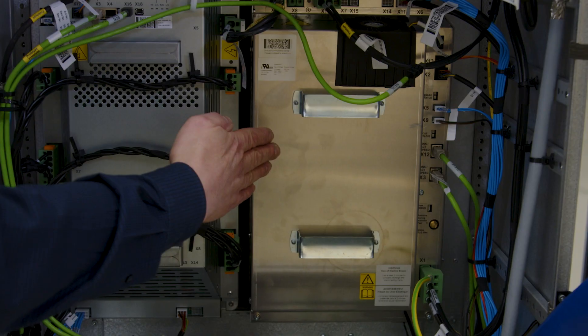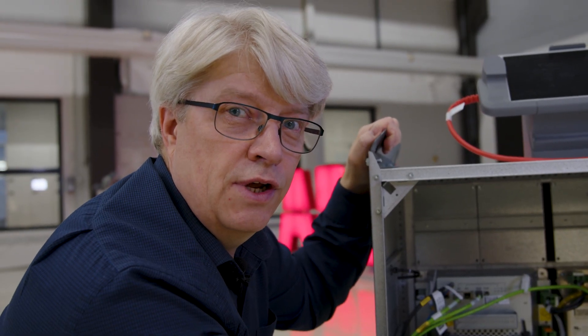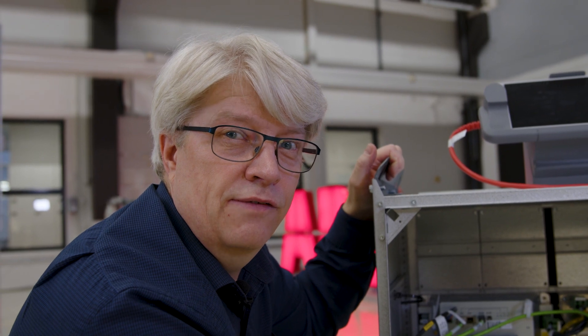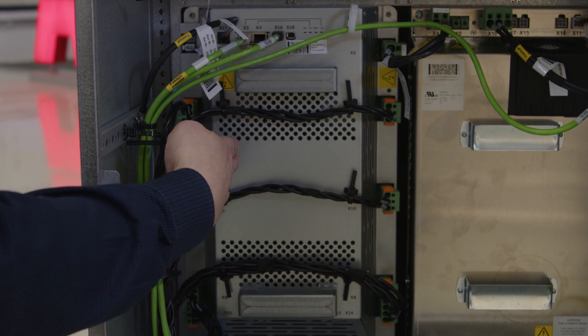Now let's have an exclusive peek inside the controller. This is the power module supporting three-phase AC input ranging from 380 volts to 480 volts. Compared to IRC5 and Omnicore C-Line, we have removed the AXIS computer. The functionality is now included in the main drive unit.